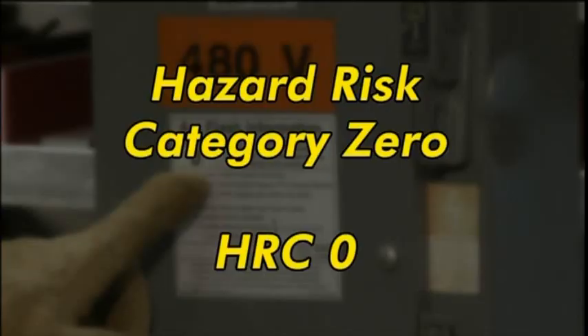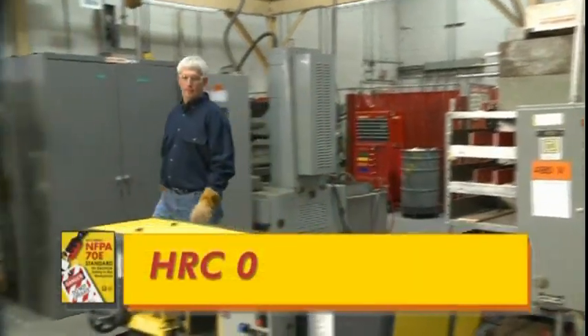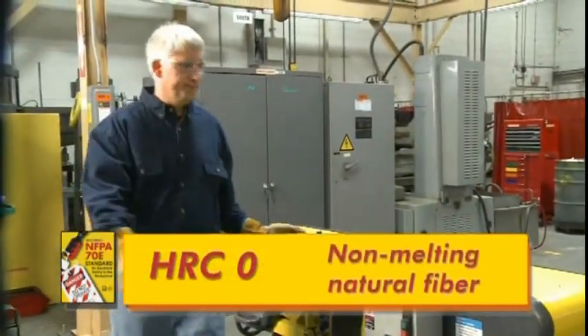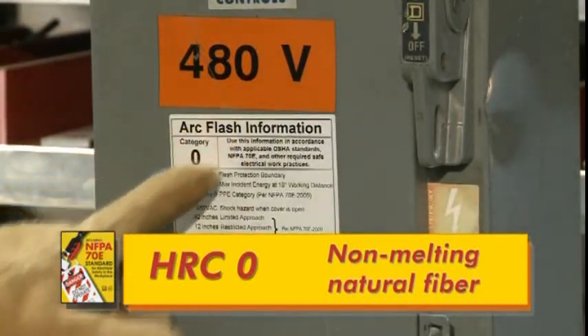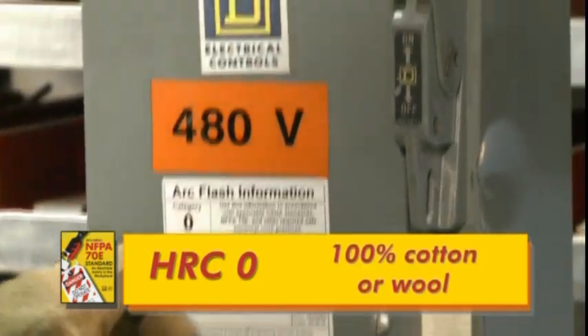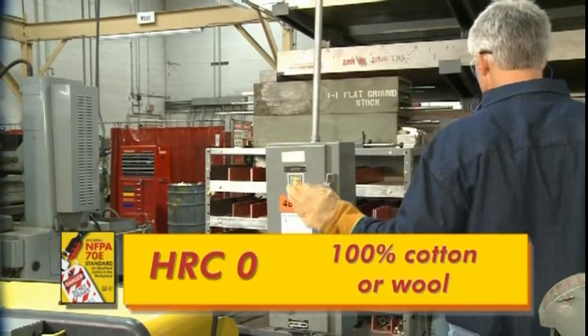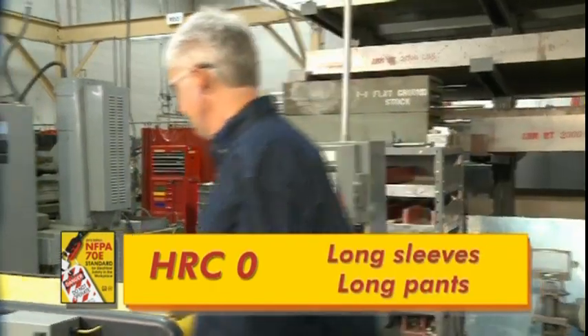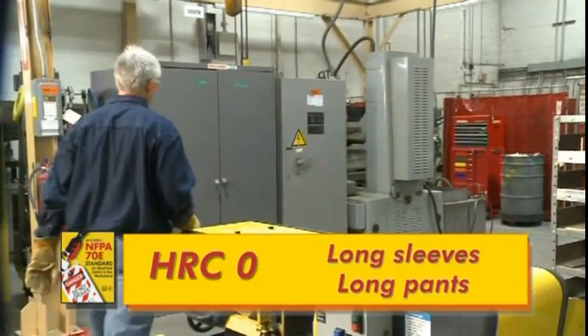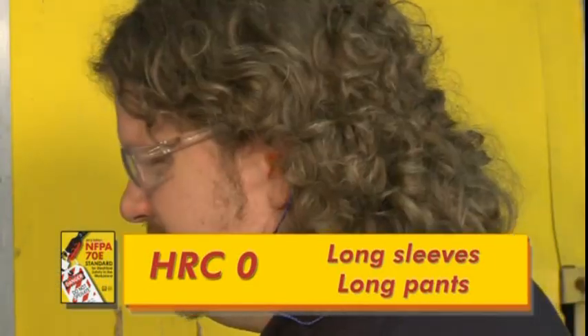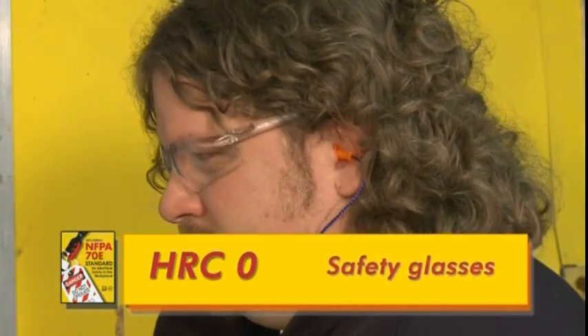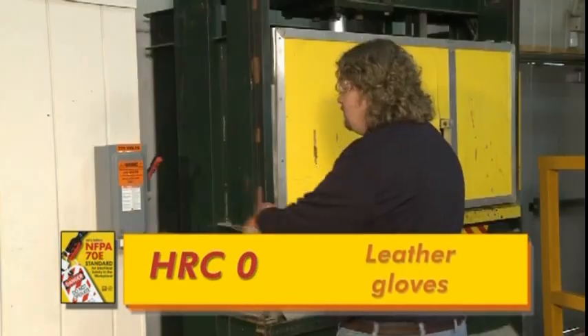Hazard risk category 0. Category 0 is the only hazard risk category where non-melting natural fiber clothing such as 100% cotton or wool is allowed. This clothing must be long sleeves and long pants. Other PPE required includes safety glasses, hearing protection, and leather gloves.